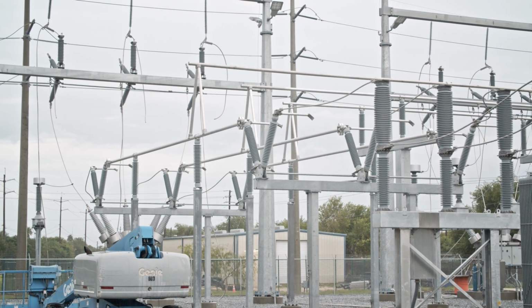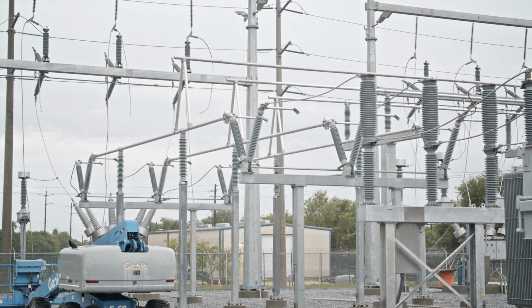The equipment outside is very similar to what we've been doing in the industry for many, many years. There's aluminum infrastructure with transformers that have copper windings with oil inside, but the significant differences are inside the substation, where we're able to manage the electricity not only to protect the grid against faults and secure the safety of people and equipment, but also to keep the lights on or transfer loads and do things much quicker using computers and very sophisticated technology. We've got some really nice state-of-the-art equipment in this station, which we're excited about.